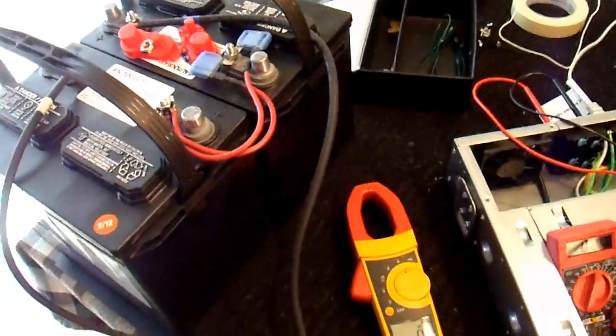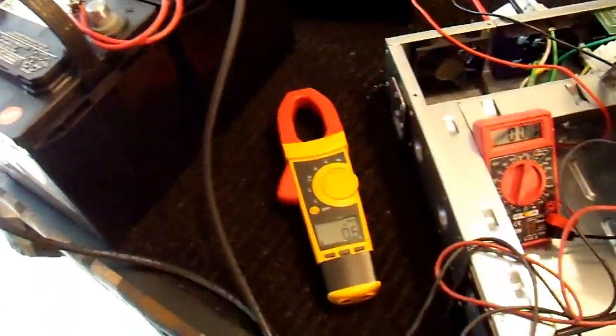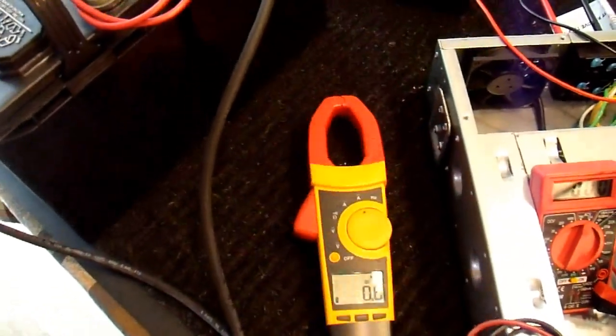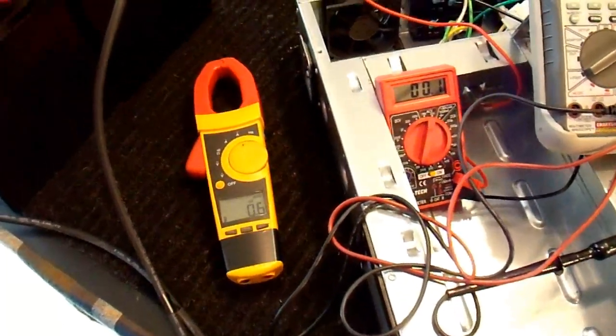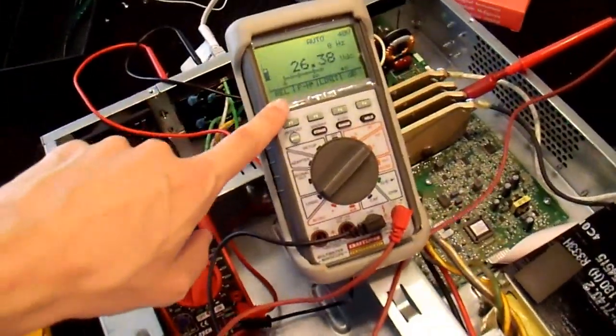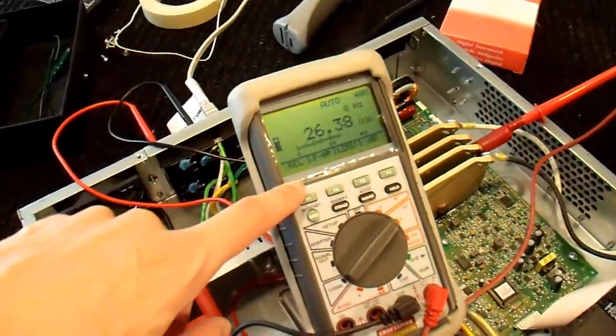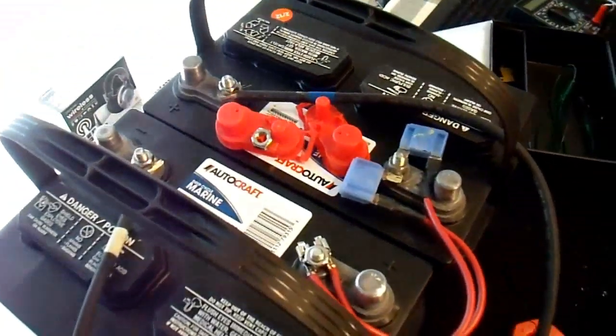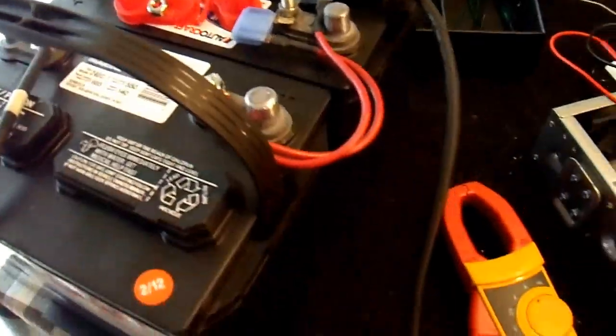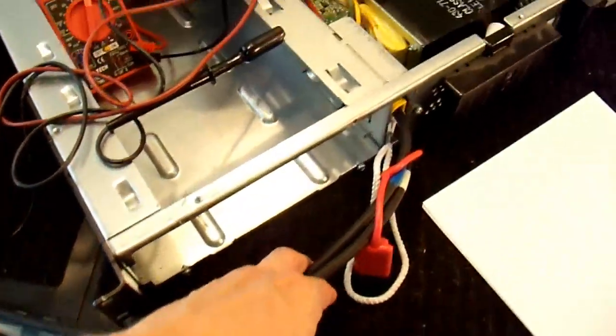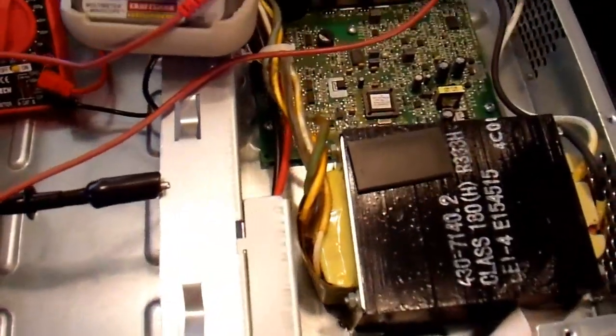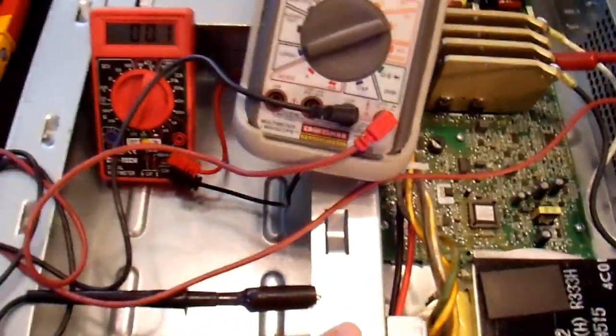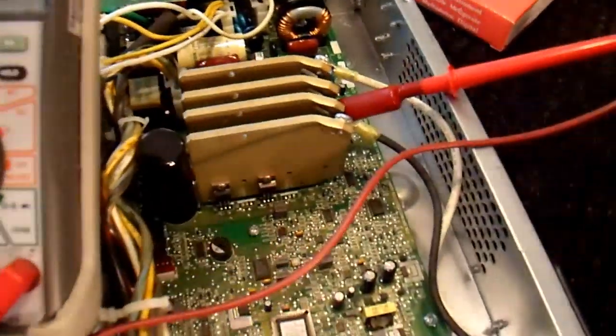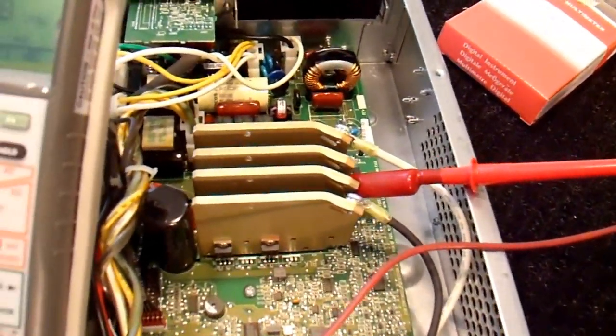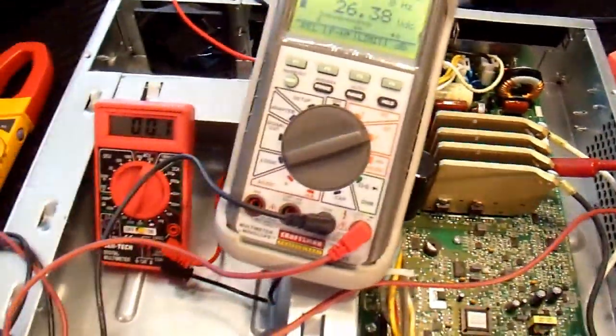To check the efficiency, I have a battery bank here, and I need to measure the input current and input voltage. For input current I'm using a clamp-on DC meter. For input voltage, I have this multimeter connected to the input voltage. I don't have it directly connected to the battery bank because there could be significant loss in the cabling, and I'm not interested in checking the quality of my cabling right now. So I have the negative lead connected to the case and the positive to the heatsink, so I'll check only the efficiency of this unit, excluding cable losses.